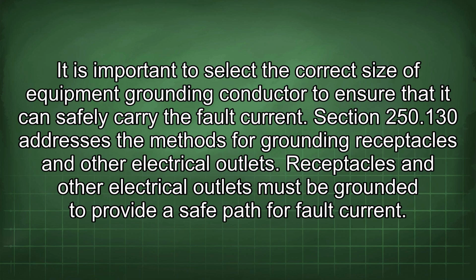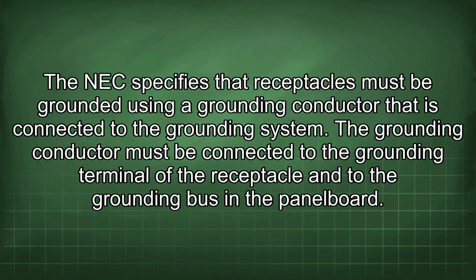Section 250.130 addresses the methods for grounding receptacles and other electrical outlets. Receptacles and other electrical outlets must be grounded to provide a safe path for fault current. The NEC specifies that receptacles must be grounded using a grounding conductor that is connected to the grounding system. The grounding conductor must be connected to the grounding terminal of the receptacle and to the grounding bus in the panel board.